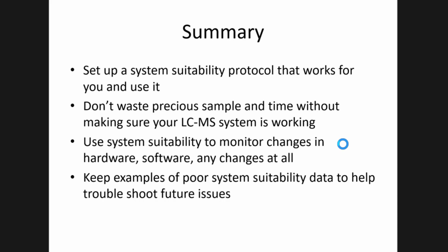And then I would be in that range. So the idea is if you start seeing your sensitivity degrade, those peak areas would go down and your percent RSDs or CVs would go up. And that would be a good indicator that you're on a threshold of the sensitivity and something might be dirty or something would need to be fixed. I wouldn't spike in hundreds of femtomoles because that's not going to tell me much about the system.